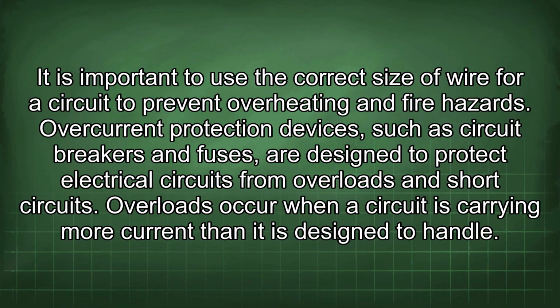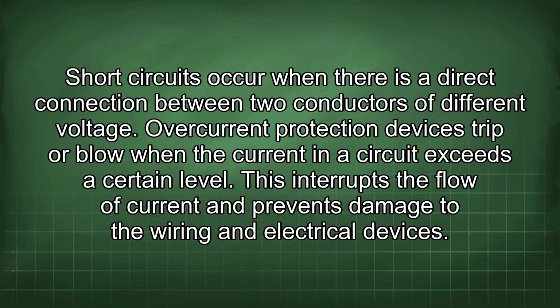Overcurrent protection devices, such as circuit breakers and fuses, are designed to protect electrical circuits from overloads and short circuits. Overloads occur when a circuit is carrying more current than it is designed to handle. Short circuits occur when there is a direct connection between 2 conductors of different voltage. Overcurrent protection devices trip or blow when the current in a circuit exceeds a certain level. This interrupts the flow of current and prevents damage to the wiring and electrical devices.